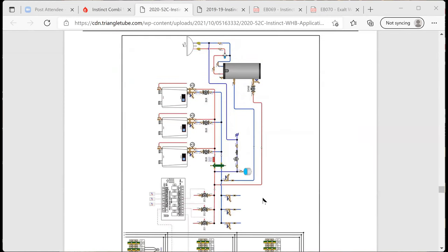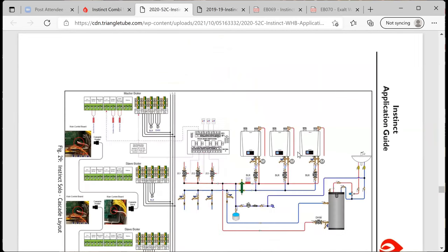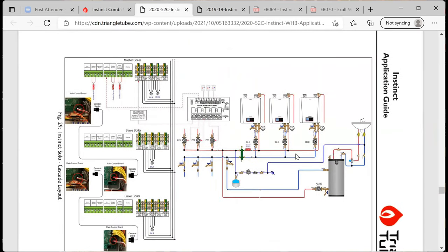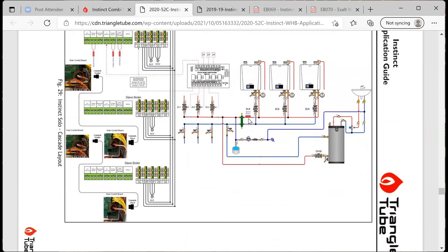This is showing cascading. So we have the supply sensor in here. Let's go here. On the low loss header, it doesn't really matter, as long as it's more of an immersion well, that's really what we gotta be concerned with. These are heating only. So we have those pumps that we've sized accordingly in here. You could do reverse return on your boilers if you wanted to, but you don't need to with ours. You don't request it. You got an indirect on the secondary side.